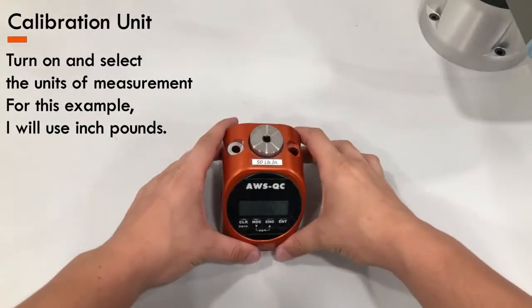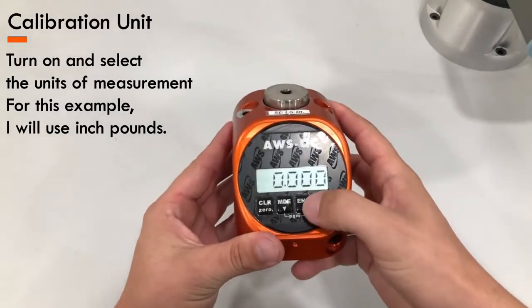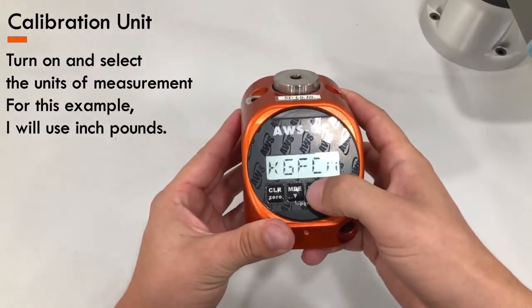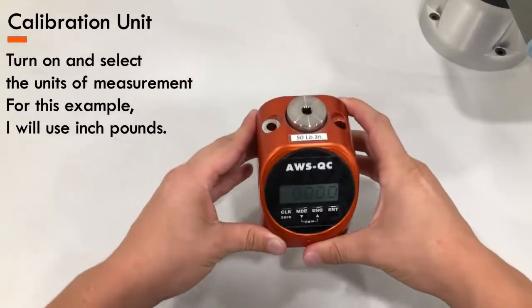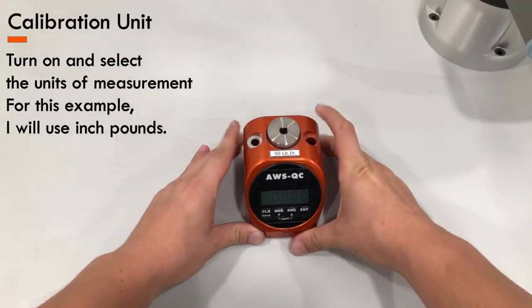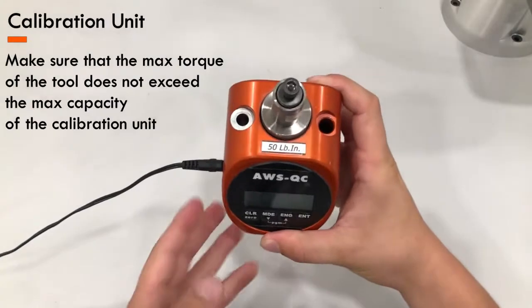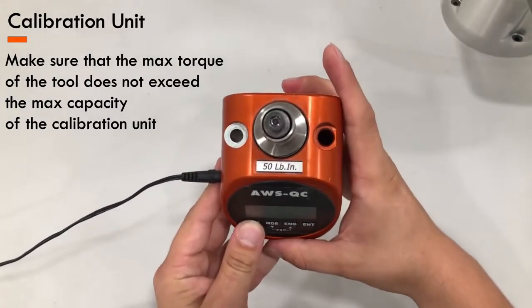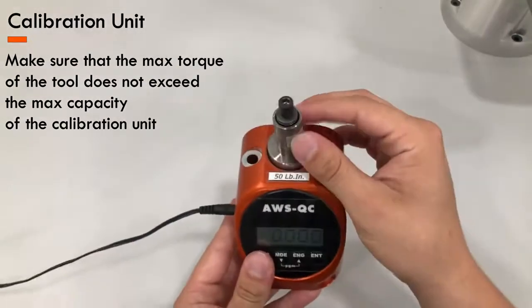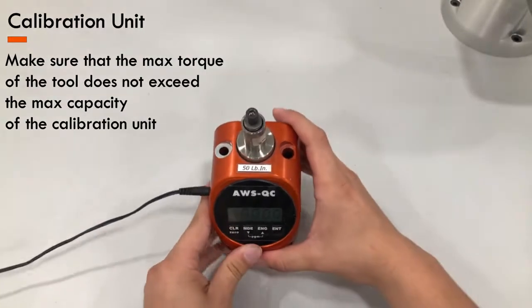Turn on your calibration unit and make sure you have the correct units of measurement selected. For this calibration unit, you can change the units of measurement by pressing on the ENG button. For this example, I will be using inch pounds. Make sure that the max torque of the tool does not exceed the max capacity of the calibration unit, because you might break or damage the transducer.